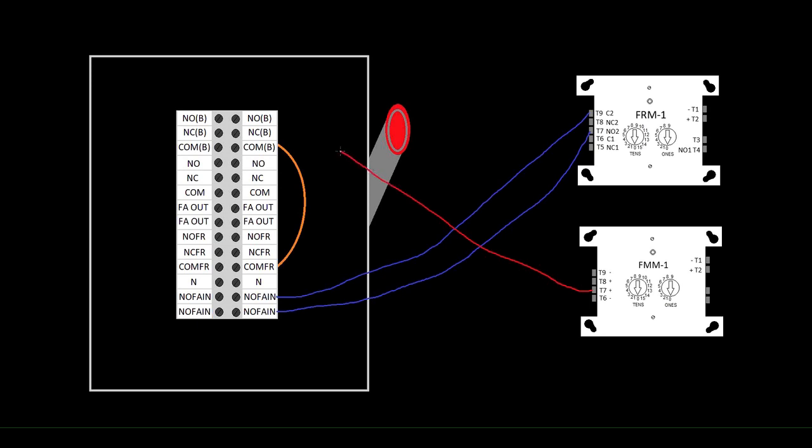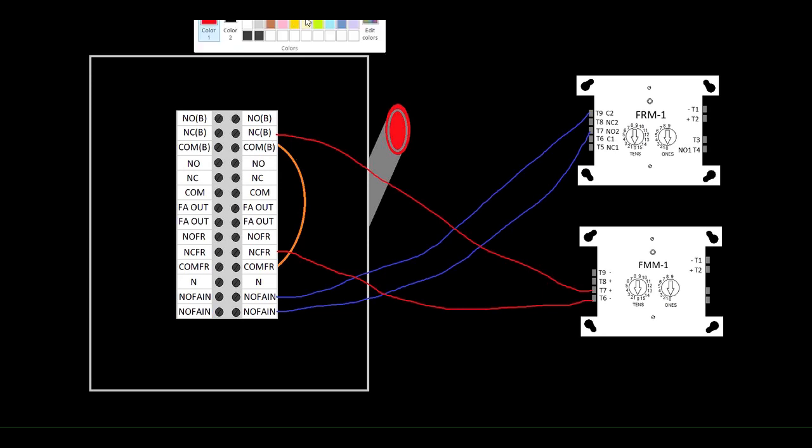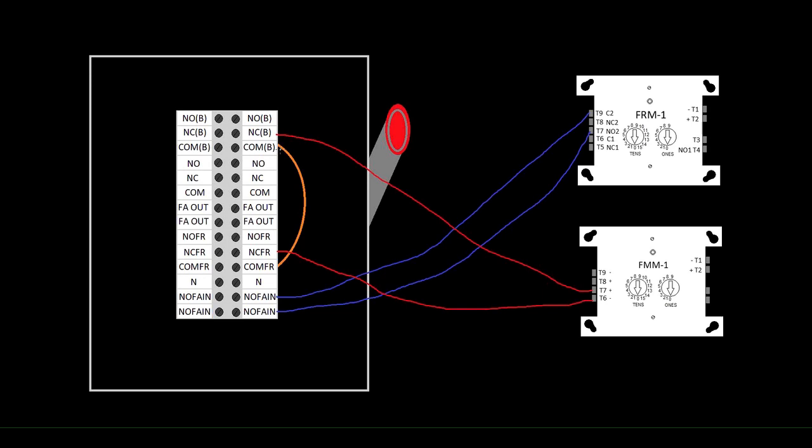Then we'll switch colors here, we're going to wire up our FMM, our monitor module. We're going to come into normally closed B and normally closed FR down here, and this orange jumper that's drawn here is factory installed. Now we'll need to install our resistor as well. The way these terminals are spaced out, you're probably going to need to, unless you've got some abnormally large 47k resistors, you're not going to be able to use the ones that come with the module or you'll have to cut it and wire nut it, but essentially we're going to come out just under the same two terminals. And you can buy this piece of equipment with a few different options, and you want to make sure that it has the option to where when you disconnect this switch it doesn't cause a supervisory, assuming you program this for supervisory.